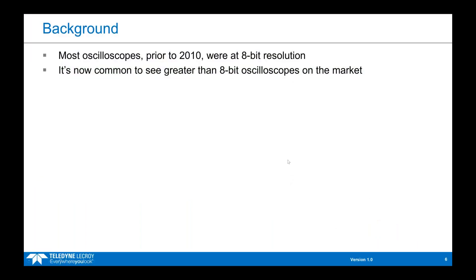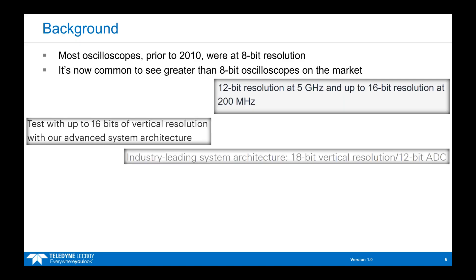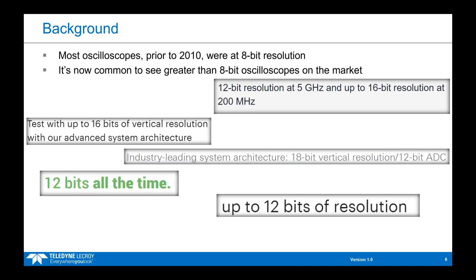A little background here. Most oscilloscopes used to all be 8-bits, and so users didn't really have to consider how oscilloscope resolution was impacting their measurements because 8-bits was all there was. But in recent years, oscilloscope manufacturers have been making a wide variety of high-resolution claims, similar to what you see here on this slide. And so it's become increasingly important to know what oscilloscope resolution is and how it's impacting your measurements.